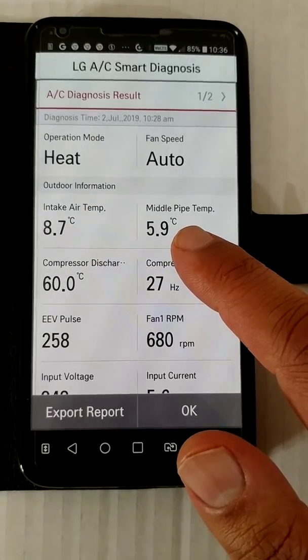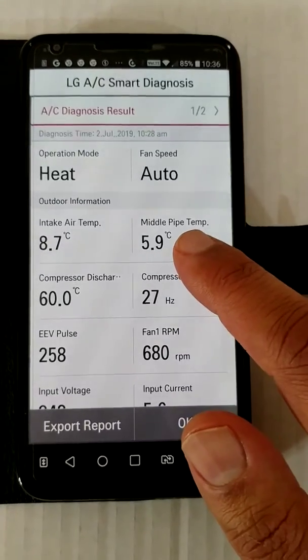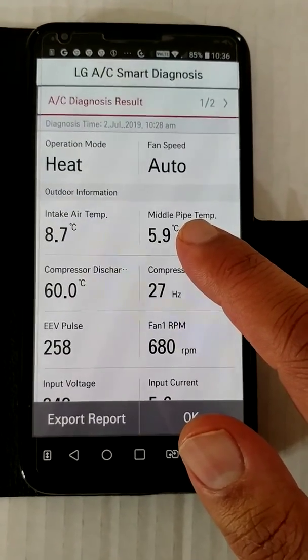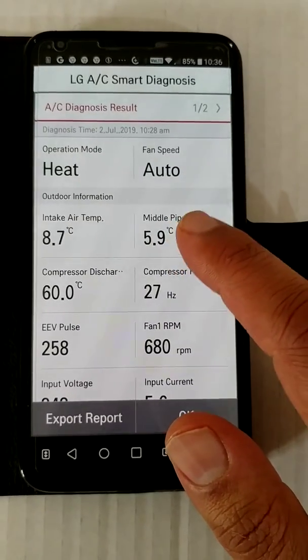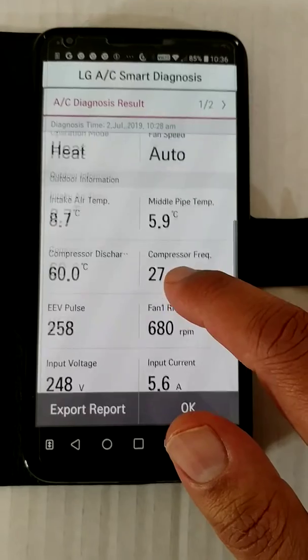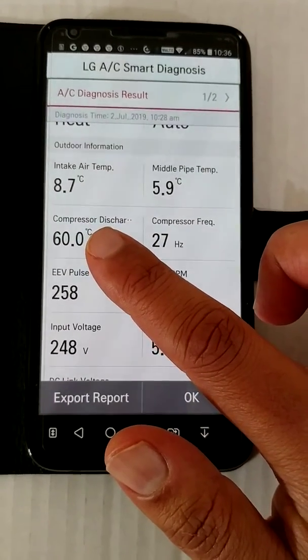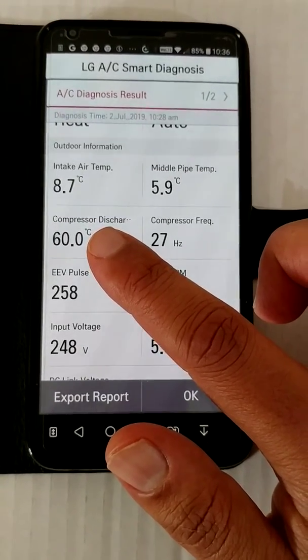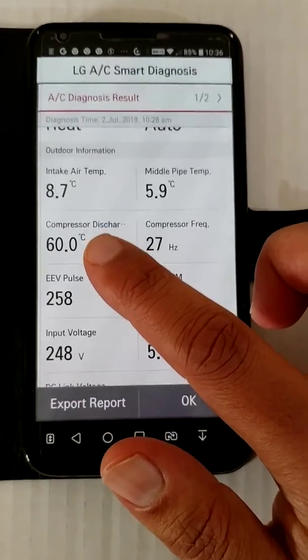Although the air is cold, the outdoor condenser in heating mode is extracting heat from the air. The compressor discharge temperature, once the heat is extracted and compressed, is 60 degrees — that's the inverter compressor discharge temperature.